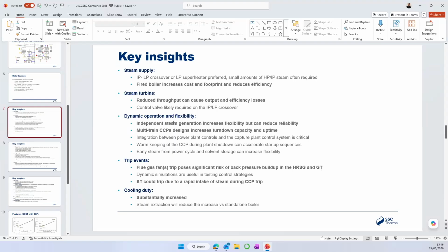Some went for it, some didn't, but all of the FEED studies fairly concluded that you can do a fired boiler or a standalone generation unit, but it will increase your costs, it will increase your footprint, and it reduces the net efficiency of the plant in most cases, especially if it's just a fired boiler. On the steam turbine side, if you're retrofitting or if you're designing your plant to operate with the capacity for unabated operation, you will likely have some inefficiencies in your LP steam turbine due to basically the fact that it's operating in an off-design condition, especially in the case of retrofits, unless you do a big reblading exercise. So that's something to keep in mind, and it can be multiple megawatts of efficiency losses in your steam turbine.